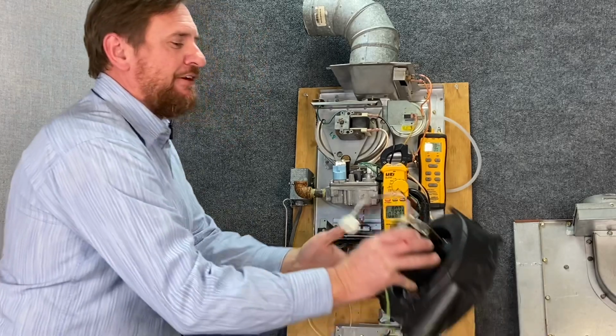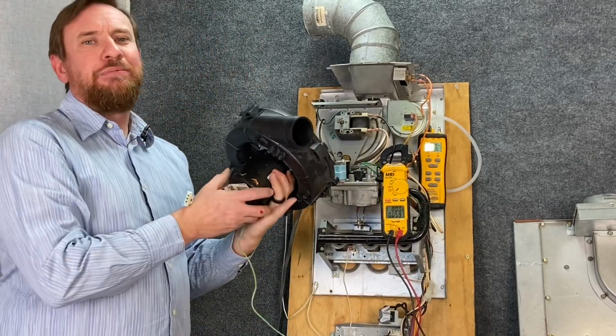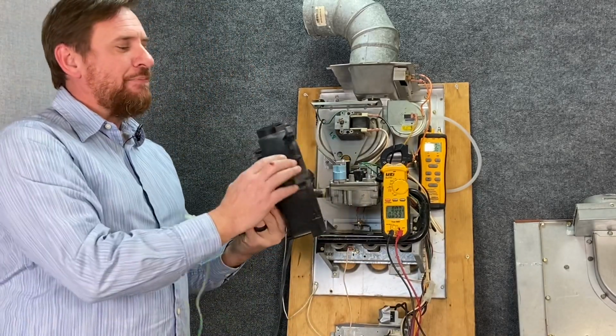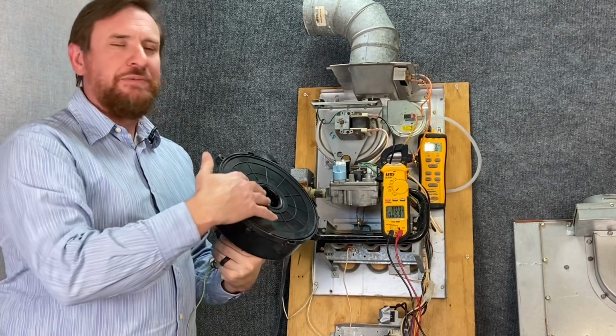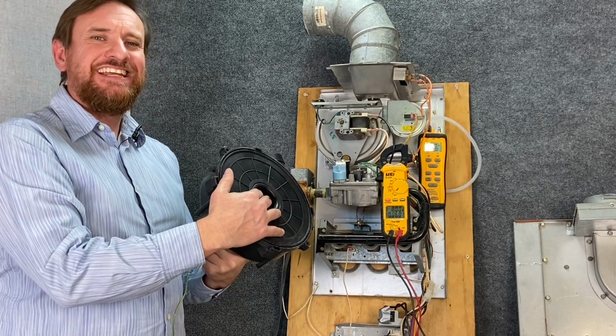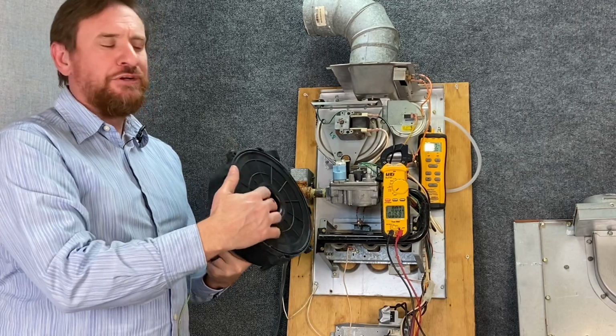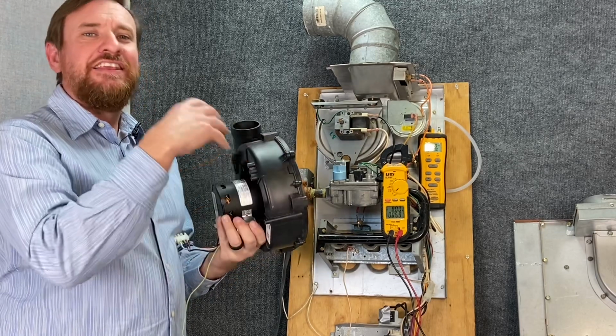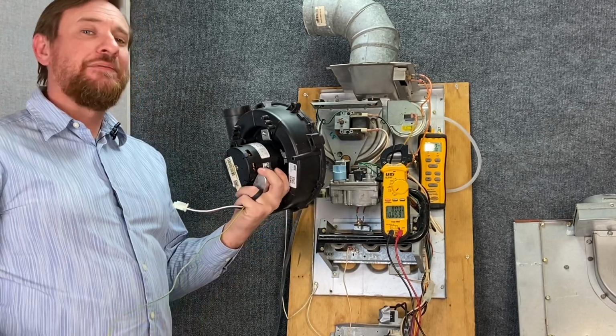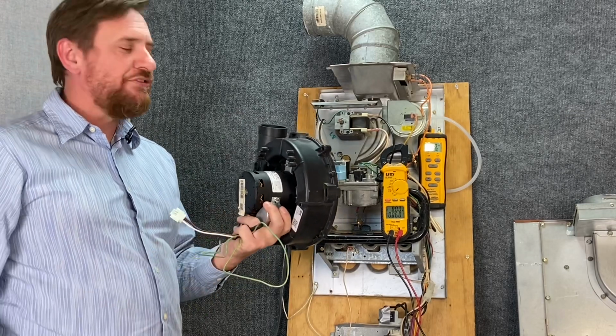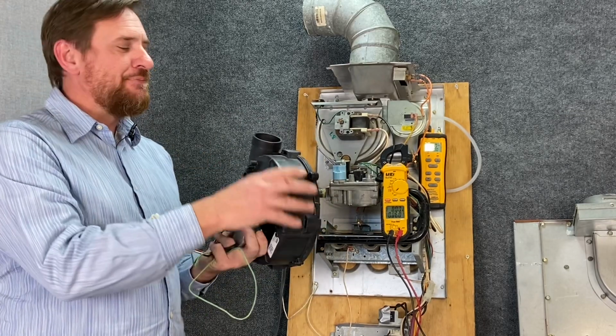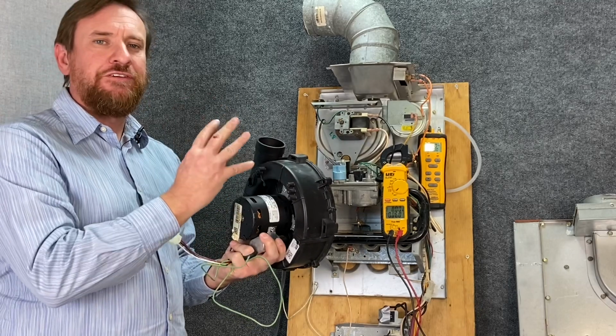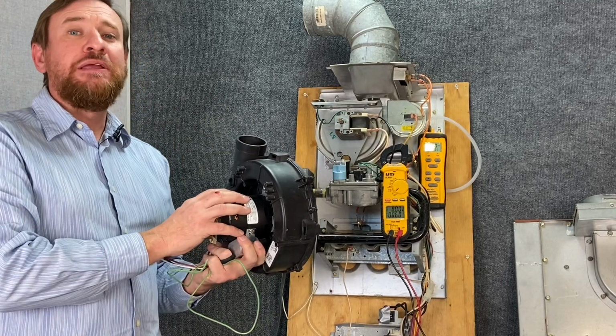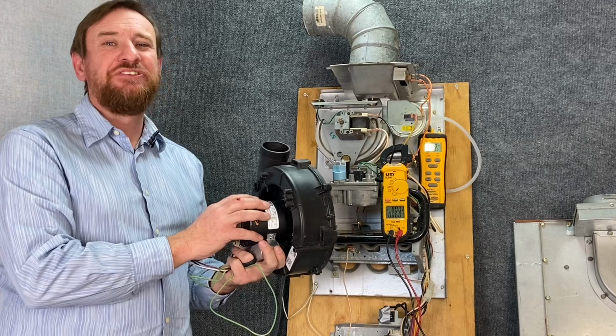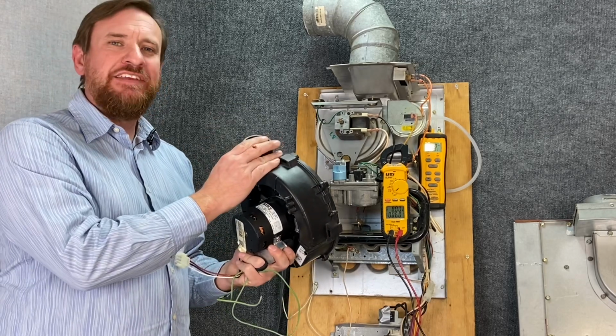The other type of furnace that we see most common is our 90+ condensing furnace. We have a plastic housing. This is because there's going to be condensation inside that heat exchanger. So we have a plastic blower wheel, and we have a plastic housing. This allows it to handle that water, and a lot of times that water, that condensate, is corrosive, so it has to be able to handle that. But this is a Category 4 furnace. Category 4 says it's going to be positive pressure and also condensing. This is going to have a PVC flue pipe.